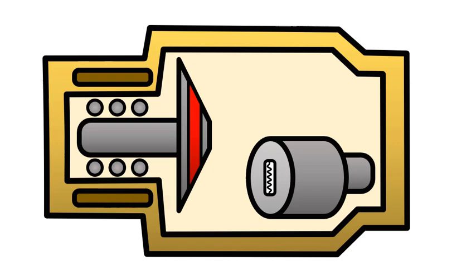And then the last part is the bearings that are in between the rotor and the rest of the X-ray tube. The bearings are low friction spheres that allow for free rotation of the rotor. During the prep phase of an X-ray exposure, you can actually hear the sound of the rotor turning on these bearings. So that is an overview of the major components of an X-ray tube.